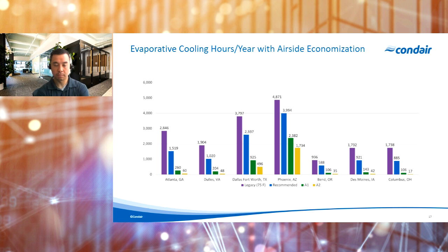As Will mentioned, since evaporative cooling technologies use very little power to operate, the primary resource being consumed is water. Therefore, reducing the hours of wetted operation is a great way to reduce water consumption and improve sustainability. One way to think about this is almost economizing your economizer. So with that, I'm going to hand back off to Will, and he's going to go over different types of adiabatic systems.